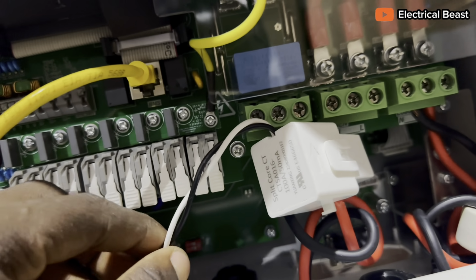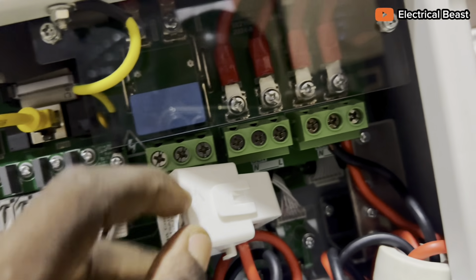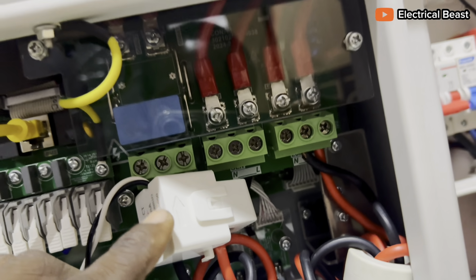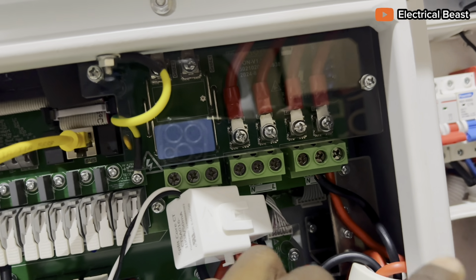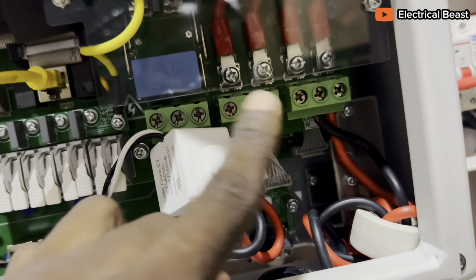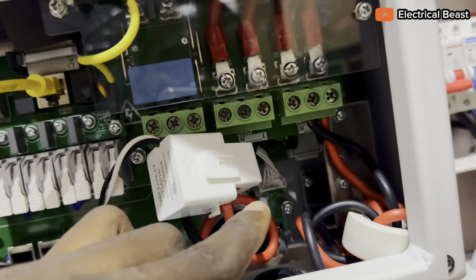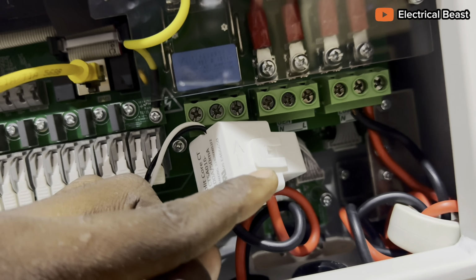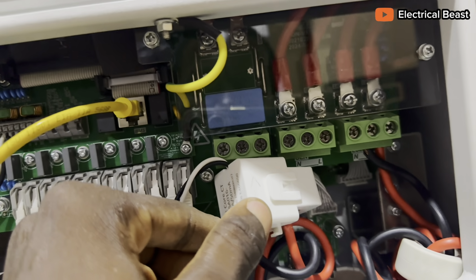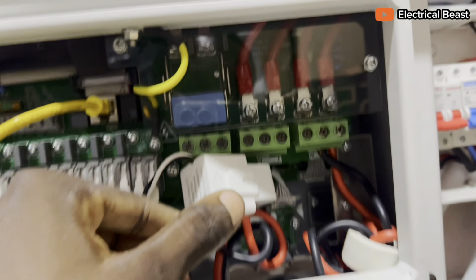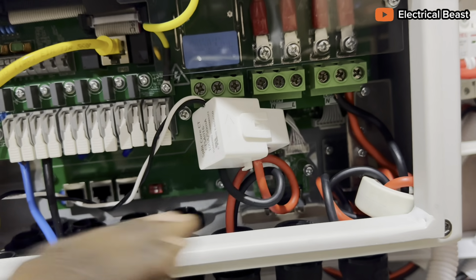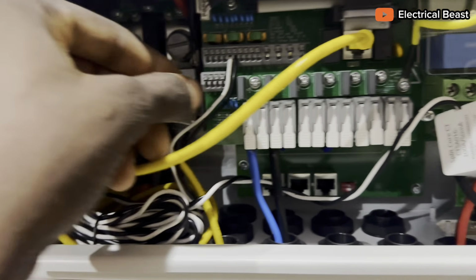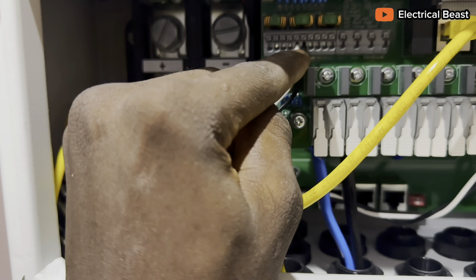If you don't want to export to grid, you connect it so this arrow faces up, meaning the current only flows in one direction, towards the inverter, from the grid - you don't want to export to the grid. So you use this, then switch on the zero export feature on the inverter, which I'll show you shortly. Then the CT connects on this address bus, to 5 and 6.